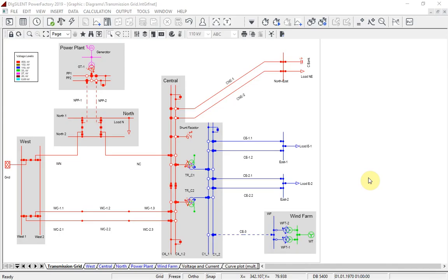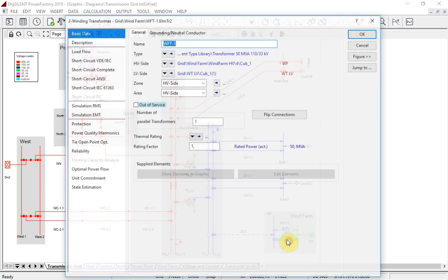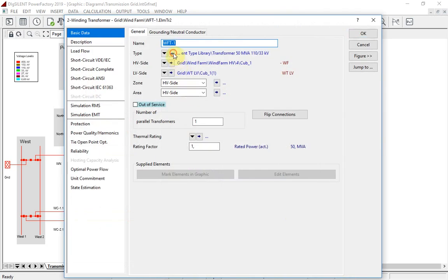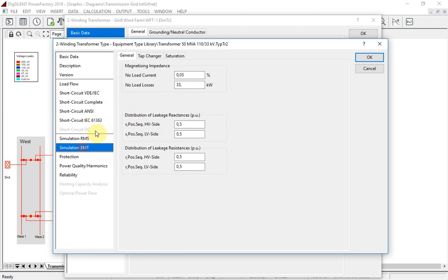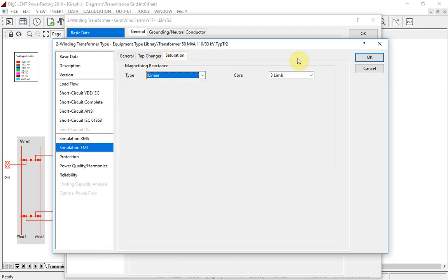There are a number of new and enhanced models available in PowerFactory 2019, and I would like to show you one example. For all transformer and reactor types, the saturation models for electromagnetic simulations have been greatly improved, making it possible to model the non-linear flux-current relationship of the iron core of such elements.